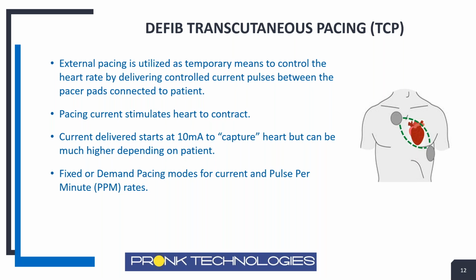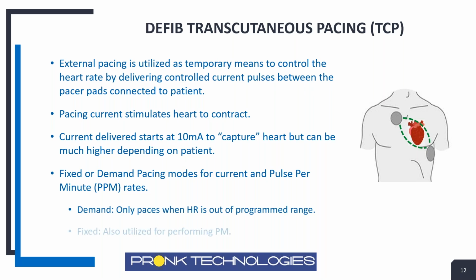Then you have the demand mode, which is, okay, we're only going to assist in the pacing of the patient whenever they're outside particular ranges. So if the patient can regulate their heartbeat within plus or minus this, then let the patient's heart do the work on its own. But if it goes outside of these ranges, then on demand, pace that patient. But we're testing it really in fixed mode only. And this is what we do during the PMs.